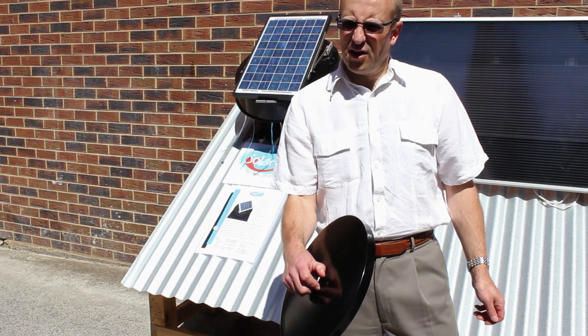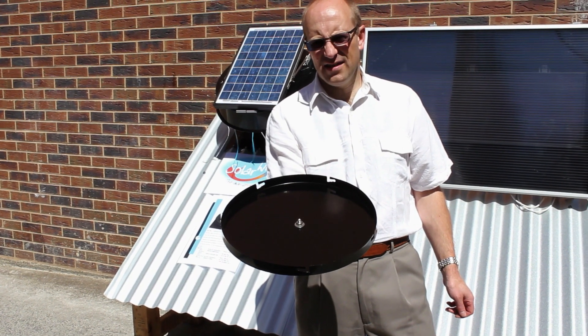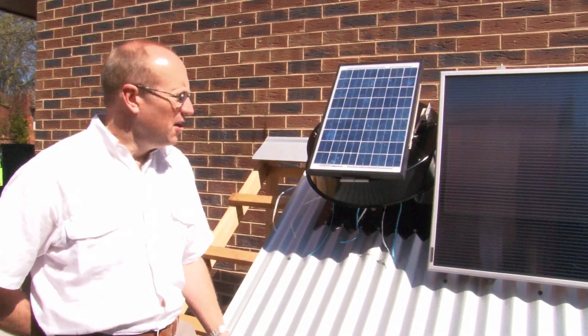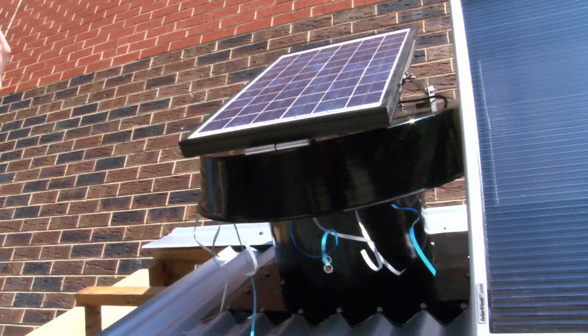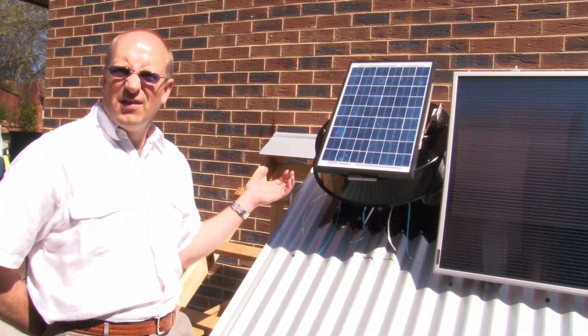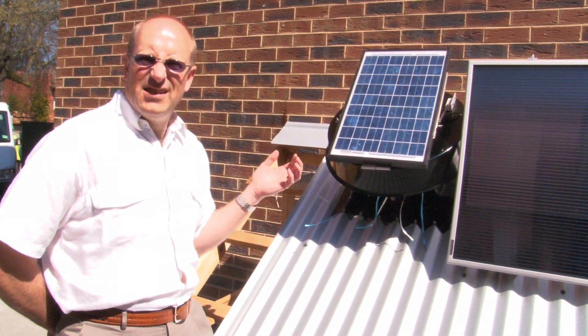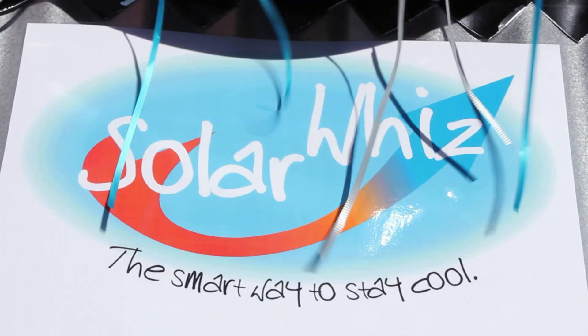The optional closing cover can be fitted to the bottom of the flashing in winter to prevent warm air from the roof space escaping. The SolarWhiz moves 1400 or 2100 cubic meters per hour, which is enough to change the air in your roof space approximately five times an hour. This constant flow whenever the sun shines enables the unit to maintain the temperature in the roof space only a few degrees over the outside ambient temperature, whereas a typical roof space would be between 60 and 70 degrees on a sunny summer's day.